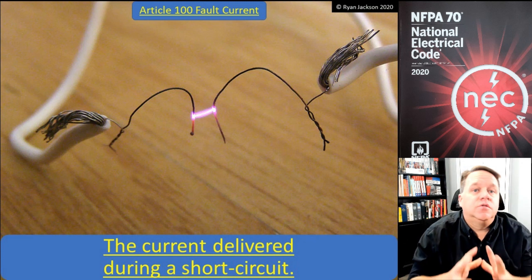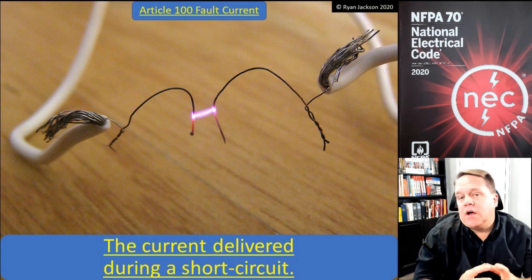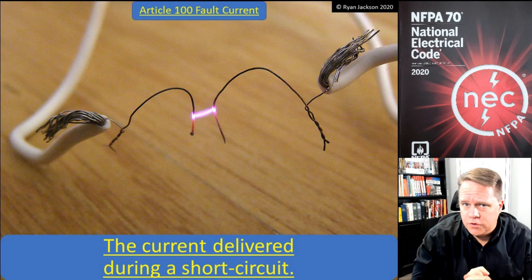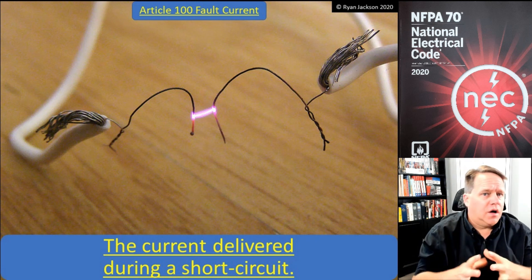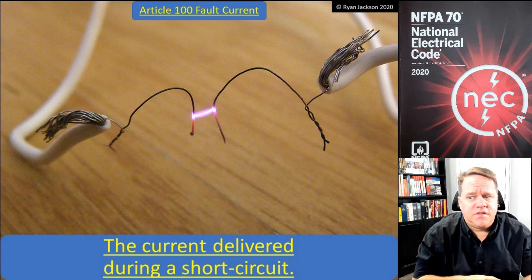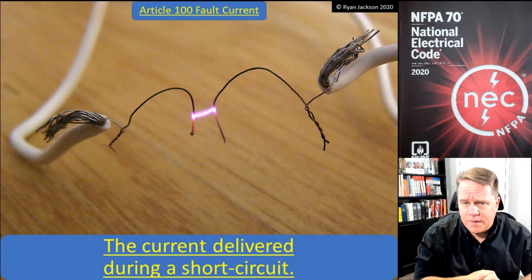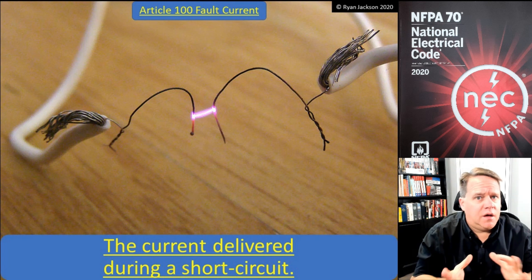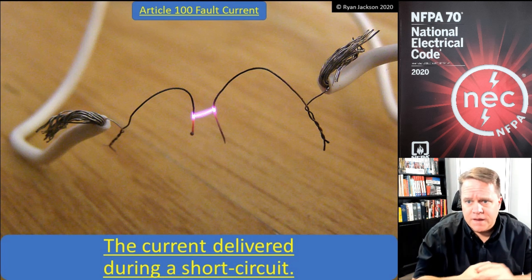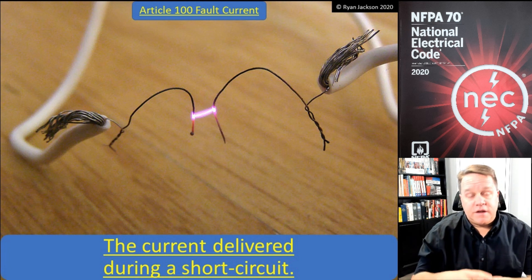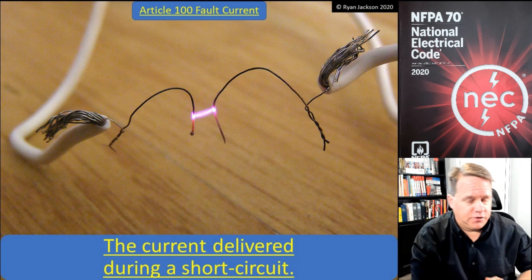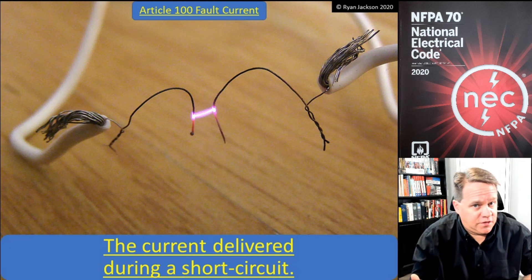The 2020 NEC added two definitions that were really important and quite frankly long overdue. We've talked about this concept in sections 110.9 and 110.10 since the 1940s. So it's about time we had these things defined. The first one is fault current, and we defined fault current really so that we could define available fault current.